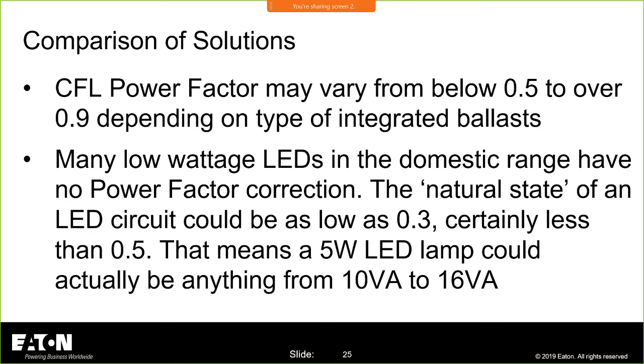So we had to make an adjustment to the ASHRAE numbers, because ASHRAE works in watts per square foot. They don't think about VA. In the National Electrical Code, we think about VA. That's how we size equipment. What we argued and settled on was a 0.8 power factor, realizing that if you bought the more expensive CFLs or more expensive fluorescent lighting, you're probably going to be up around 0.9 and maybe a little bit better. In fact, to have an Energy Star related lighting product, you have to be greater than 0.7. I think it's 0.7 or 0.75. I've got it in my presentation here somewhere. But I did find that a lot of these less expensive fluorescents are at 0.5. And we all know where in our industry most of our solutions get bought. They come from low bidders, and they're not buying the more expensive fluorescent tubes. They're going to be buying the less expensive ones.